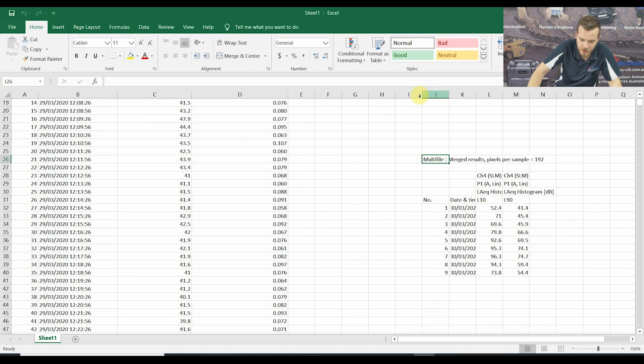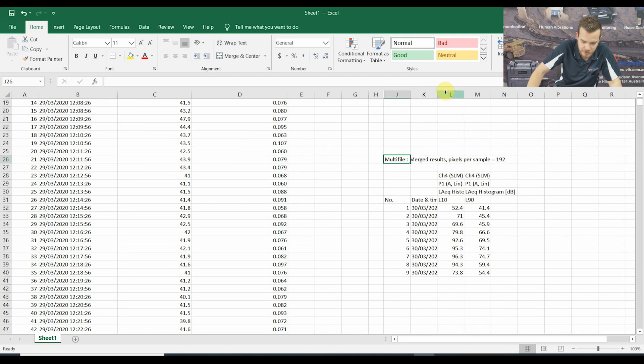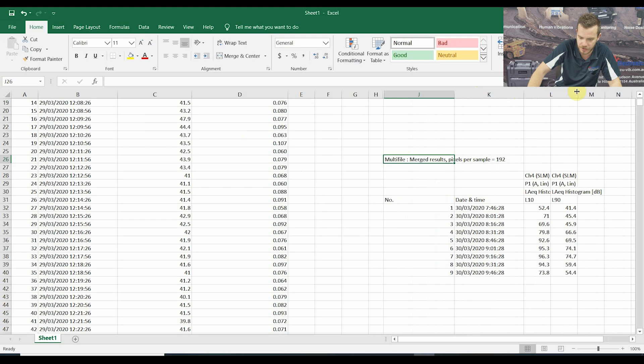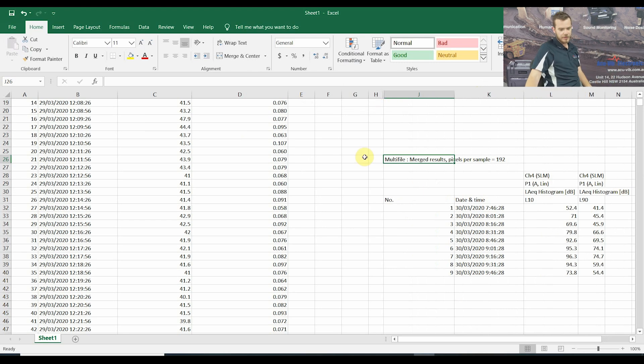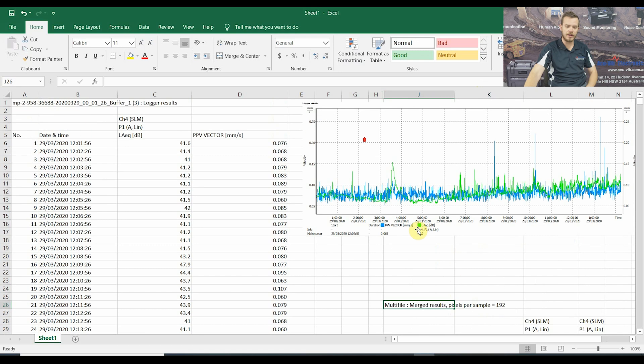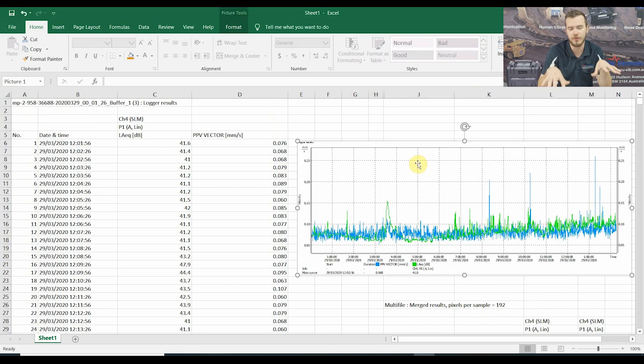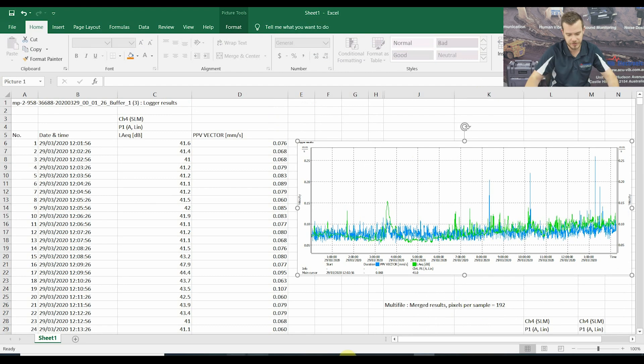We've got our statistical data. Same thing — grab the whole table and merge this to Excel, using the same sheet we're working on. Now we've got our statistical data in the same worksheet as our other results. For a lot of environmental logging, this is all the data you need. You can send this to your client, make your own reports, and that's basically a simple way to export data from SvanNet, analyse it, and put it into Excel.